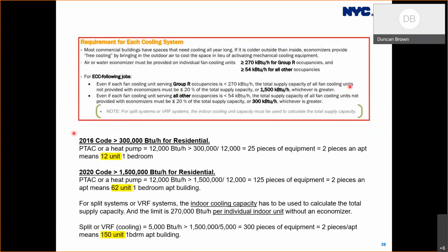So as a brief example, with the 2016 code, the limit being 300,000 BTUs for residential. Let's imagine a typical PTAC or a heat pump that was 12,000 BTUs, or like 1 ton. Then dividing the 12,000 into 300,000, the limit, that would give you 25 pieces of equipment. And let's say it's a 1-bedroom apartment. That would basically be a 12-unit building. With the 2020 code, with the limit raised to 1,500,000 BTUs for residential, with the same PTAC heat pump size, you can now have 125 pieces of equipment. And at 2 pieces an apartment, the living room and the bedroom, that would mean a 62-unit apartment building. So a much bigger increase.